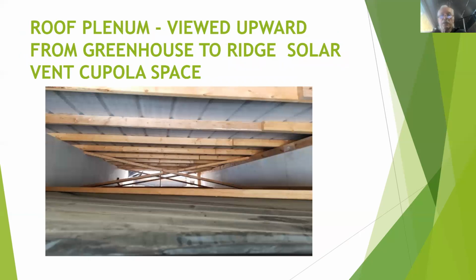The hot air supplied ultimately to the ridge solar vent cupola comes from these north and south roof plenums, created by the large space between the upper steel roofing and lower ceiling insulation panels. These pre-stressed ceiling panels are constructed kind of like a sandwich, using two layers of foam separated by an airspace with high density foam spacers. This polyurethane foam adhesive, when put inside a clamp fixture, results in an extremely strong and lightweight panel that can span longer distances with a high R value.